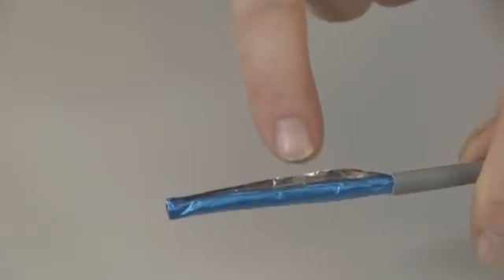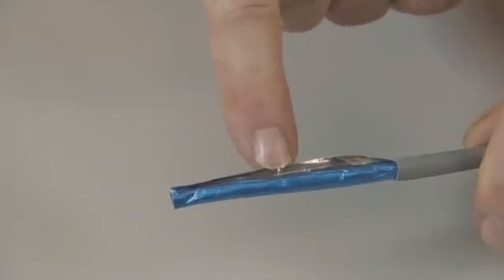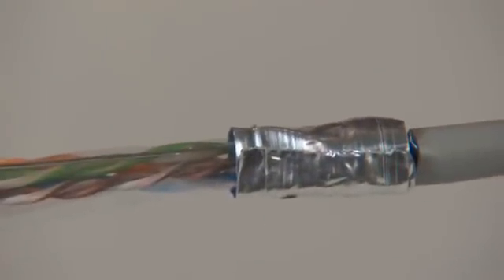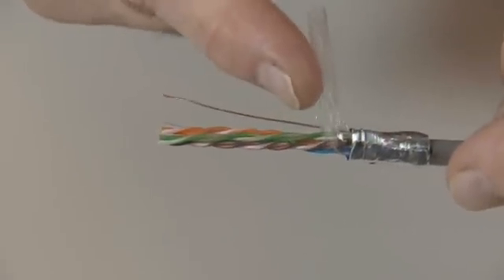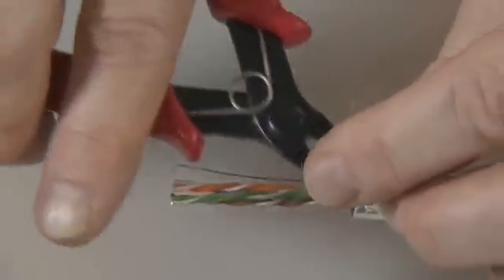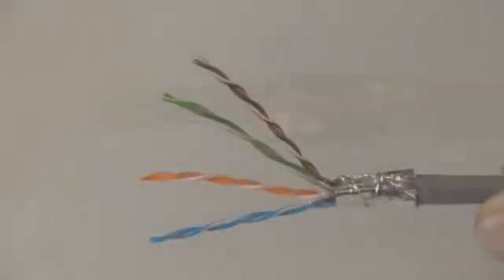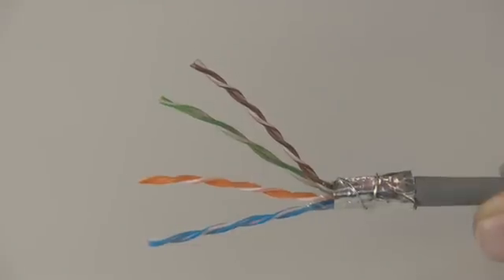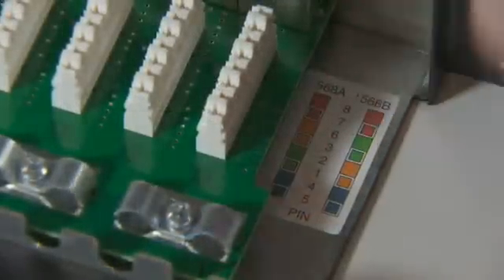Wrap the foil around the four wire pairs. Remove the Mylar wrap and then wind the drain wire around the foil. Separate the wire pairs. Select the appropriate wiring code, T568A or T568B.